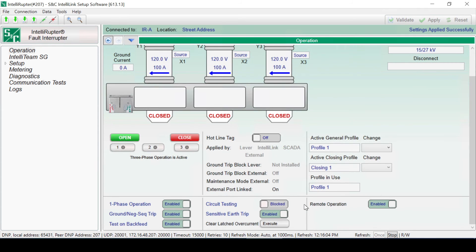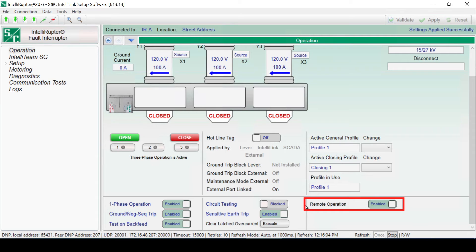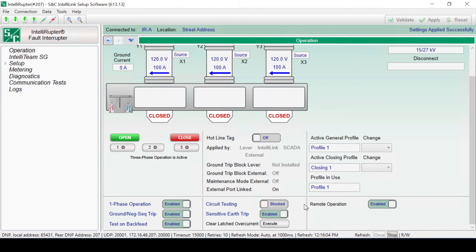The Remote Operation button is used when there is a need to prevent remote operation. If you are connected via IntelliLink software and this button is clicked, it will disable all controls and will require reconnection via Wi-Fi to re-establish the ability to use the controls. SCADA control will also be lost if remote operation is disabled.